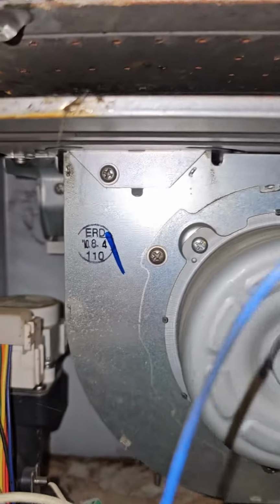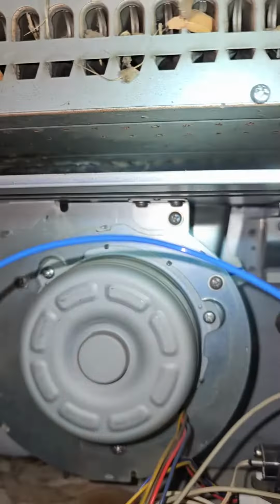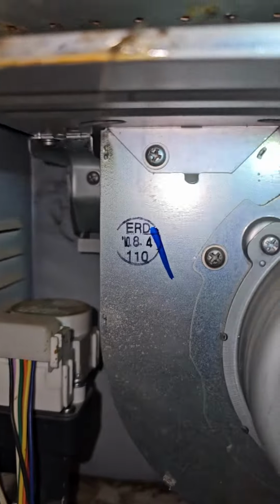We even have small pieces of wood chips inside of here. And we're also dealing with some leaking through the primary heat exchanger of the NR083 DVC direct vent. We do have a leak in the heat exchanger, and that's where that water's coming from back there.